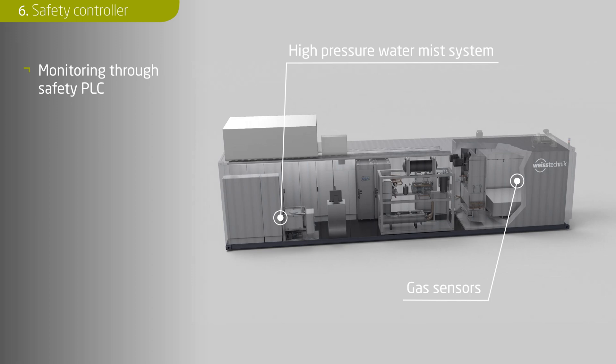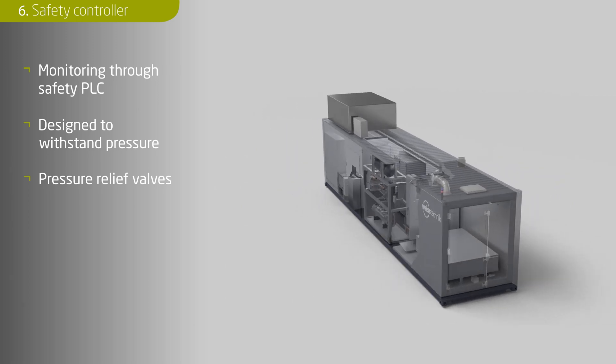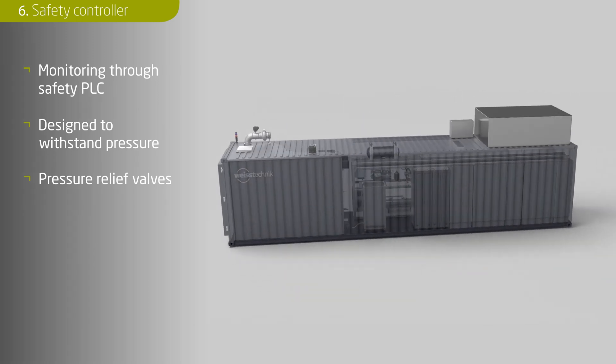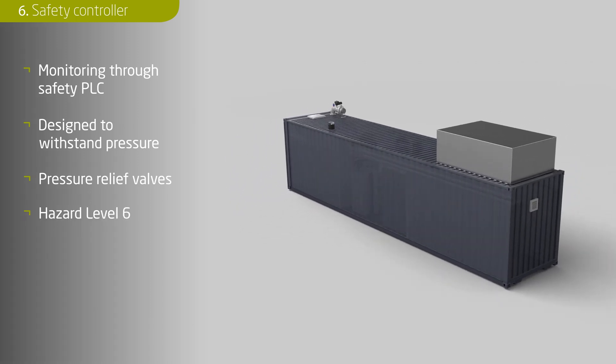Furthermore, the safety PLC monitors sensors for locking the doors, warning lights, horns and emergency stop switches. Pressure may rise in the climate chamber in the event of battery damage. For safety reasons, the climate chamber was designed to withstand pressure and relief valves were installed in the roof. All safety measures are designed in accordance with the Weiss Technik standard at hazard level 6.